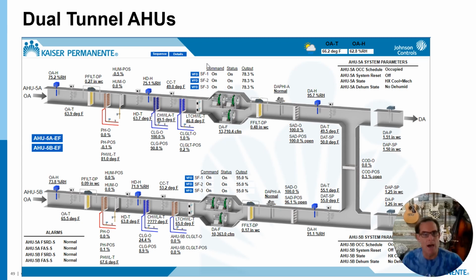So this is not N+1. This is not a 100% redundant design on the air handler capacity, but this is a design where we could essentially lose an air handler, take an air handler out, and we would have partial capacity because the other air handler would continue to serve the space. So the added cost here is really the cost of the cross connection.